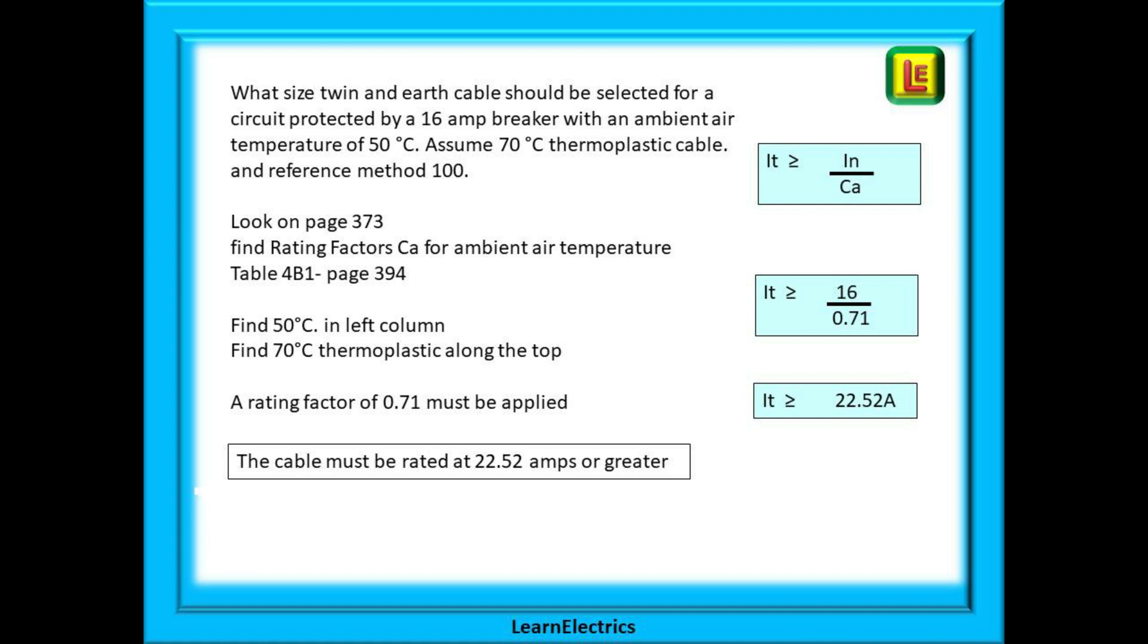This is table 4B1 and you will find this on page 394. Find 50 degrees in the left column. Find 70 degrees thermoplastic along the top and where they cross tells us that a rating factor of 0.71 must be applied. Divide IN the size of the breaker which is 16 amps by 0.71 and the new tabulated rating is 22.52 amps.